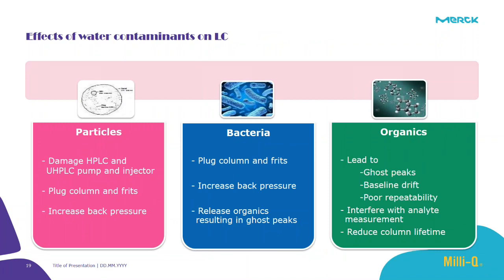In this slide, we will show some contaminants, and we'll see the effect of contaminants on your instrument itself. First contaminant we have is particles. Particles can cause severe damage to HPLC and UHPLC pumps and injectors. They can block the column and frits. It can increase the back pressure as a result.